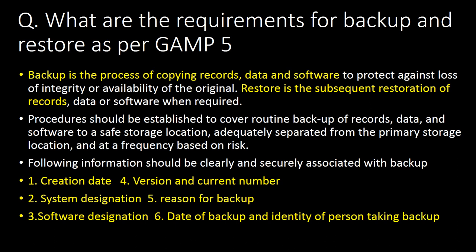What are the requirements for backup and restore as per GAMP-5? Backup and restore are two different concepts. Backup is a process of copying records, data, and software to protect against loss of integrity or availability of the original. Restore is the subsequent restoration of records, data, or software when required. A procedure should be established to cover routine backup of records, data, and software to a safe location, adequately separated from the primary storage location, and at a frequency based on risk.